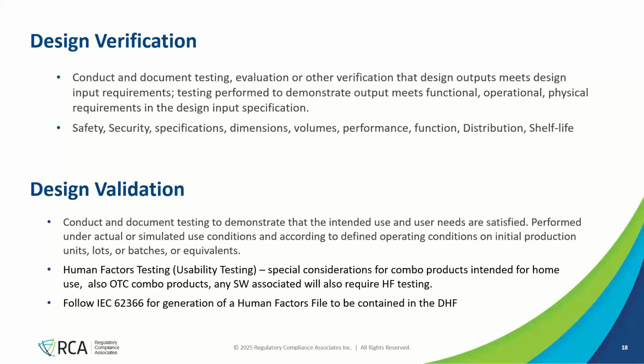So that is design verification. And then design validation is testing that demonstrates you've met the intended use and the user needs. Typically performed under actual or simulated use conditions according to the defined operating conditions on initial production units, lots or batches, or something you can justifiably call equivalent.